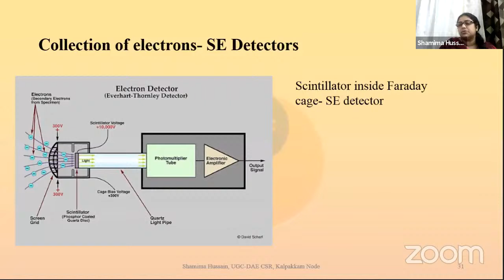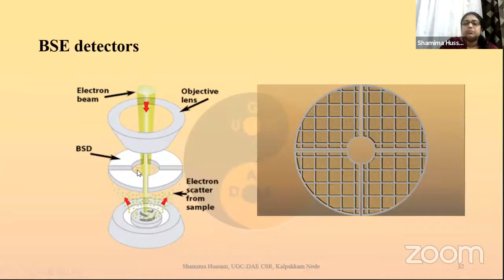If I were to detect BSE, then I would reduce this voltage to 100 volts, because BSE come from within the sample. As we saw earlier, they would not have such high energies. So that is why we cannot use the Everhart-Thornley detectors, because as we mentioned earlier, these electrons have lesser energy. So this kind of four-set quadrant detector is what we have here to collect our electrons for the BSE mechanism.